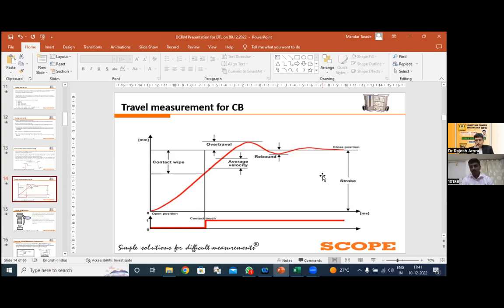I'll just repeat the things. Here we are taking the reference of the first contact touch. From the 0th position to the first contact touch point will give you the idea about the contact gap. From the first contact touch to the travel rest, or the mechanism stabilization, that delta gives you the value of your contact wipe. And from the 0th, where the mechanism is idle with no movement, to the second, where your mechanism has rested completely, the delta between these two gives you the idea about your total travel value.